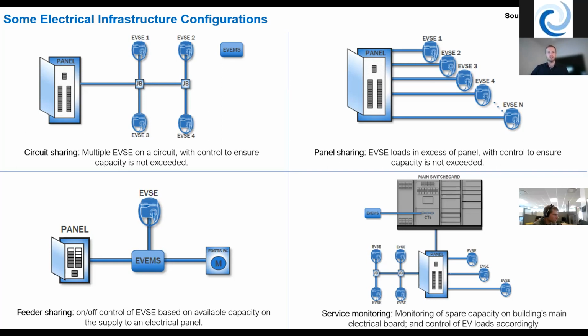And then here, bottom right, is service monitoring. Service monitoring is where you're actually monitoring the main electrical service into a building, in this case, a larger multifamily building. You've got a current transformer, a little monitoring device on that main service, and it's ensuring that the building isn't approaching the capacity of that service, of the building's main transformer, or of a major feeder. As long as there's capacity there, it's communicating to the charging station saying, yep, continue charging, you're okay. And if there isn't capacity, it says, throttle down or turn off, there's not capacity right now for you to charge. And that ensures that you're not going to exceed, let's say, a limit like 80% of that building service.